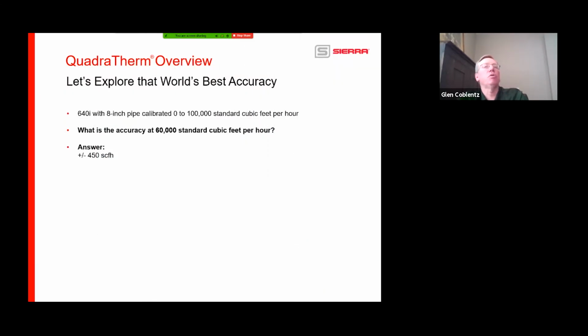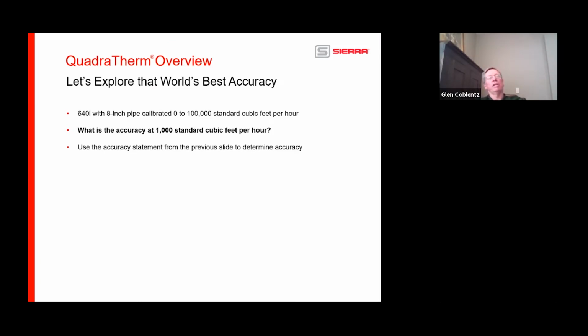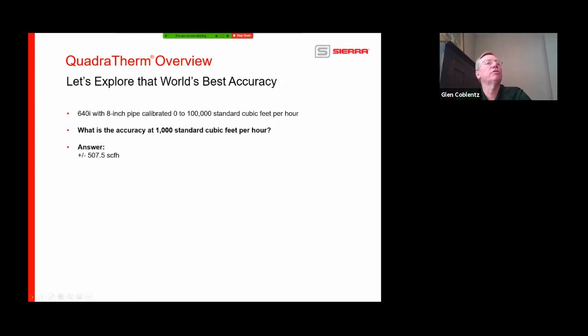All right, let's do this one more time so we get familiar. 640i, 8-inch pipe, 100,000 standard cubic feet per hour. What is the accuracy at 1,000 standard cubic feet per hour? Again, I'm looking for the answer in the chat room. This was a little bit more involved because this may or may not be below or above 50% of the calibrated full scale. It should be clear looking at it that it's below 50% of the calibrated full scale. And now we have an answer. Very well done. The answer is plus or minus 507.5. So let's see how we did the math on that.